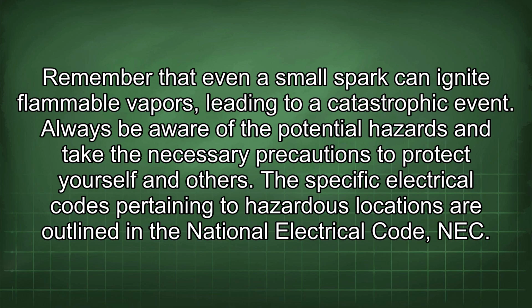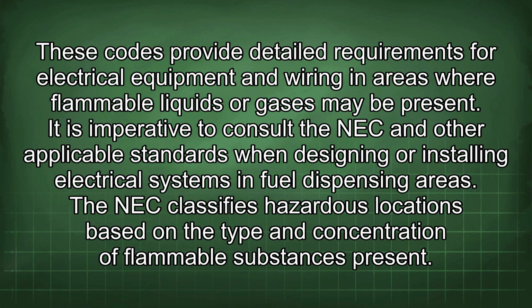The specific electrical codes pertaining to hazardous locations are outlined in the National Electrical Code (NEC). These codes provide detailed requirements for electrical equipment and wiring in areas where flammable liquids or gases may be present. It is imperative to consult the NEC and other applicable standards when designing or installing electrical systems in fuel dispensing areas. The NEC classifies hazardous locations based on the type and concentration of flammable substances present.